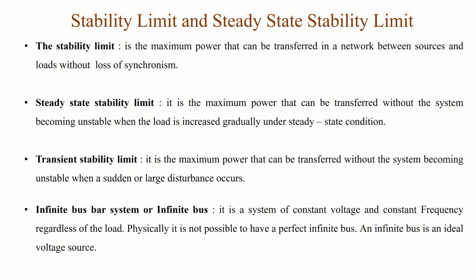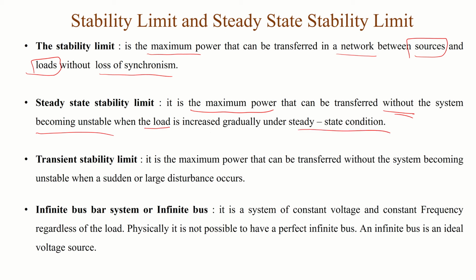Now the stability limit and the steady state stability limit. The stability limit means the maximum power that can be transferred in a network, between sources and loads, without loss of synchronism. The steady state stability limit is the maximum power that can be transferred without the system becoming unstable when the load is increased gradually under steady state condition.